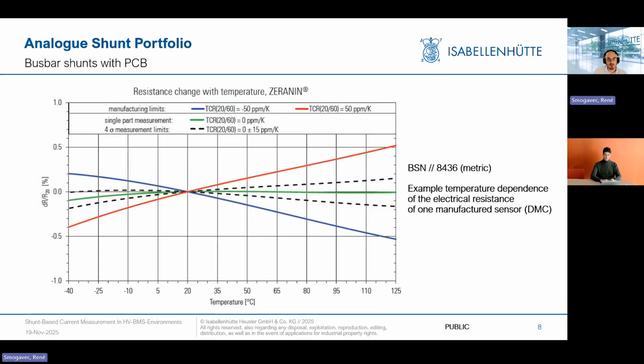So if you use your AOI and scan this DMC, you're able to flatten the curve way more over the whole temperature range, which is not neutralizing the whole temperature dependency, but if you look at the dotted lines, it's more or less plus minus 0.2% for the whole range, or between -10 and roughly 65, it's even 0.1.